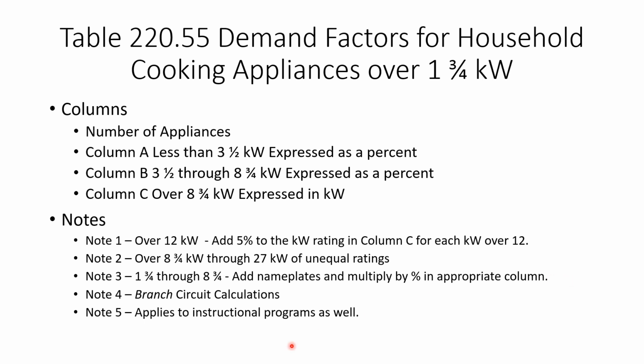And then note 5 is interesting because it's not very complicated. It just applies to instructional programs as well. So if they say, which can be a little confusing if you didn't realize this, because you might be tempted, if they were talking about some type of home ec class or something like that, you might say, well, that sounds commercial to me. Well, it's not commercial. You don't go to what they call the other than dwelling. A home ec class or an instructional institution is figured exactly the same as a dwelling. All right, so that's interesting.